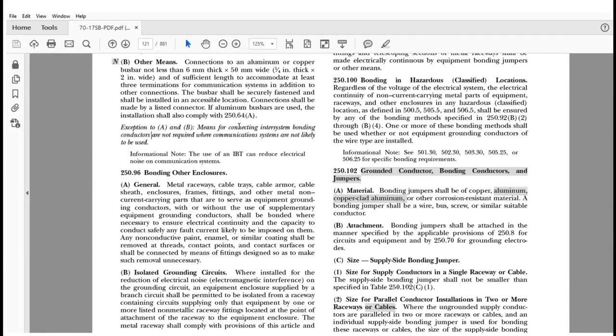I would not say that's the case on any commercial building or industrial building or a residential type building. But you might have a structure that is a tower, or you might have a structure that is something else, where you can argue the point that you're not going to have these communication systems, and you can actually use this exception and convince your local inspector of the unnecessary need for this type of connection. So you did get this exception in there to help you. This is a new exception.